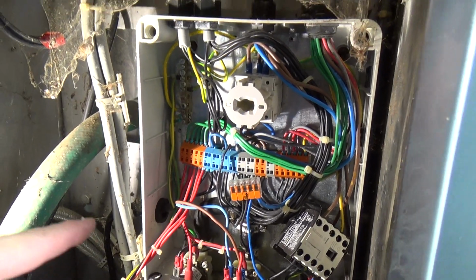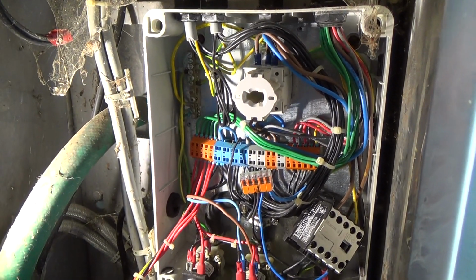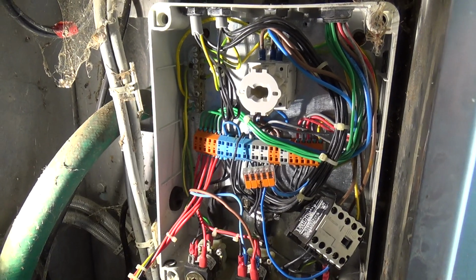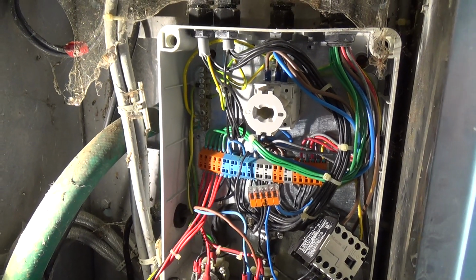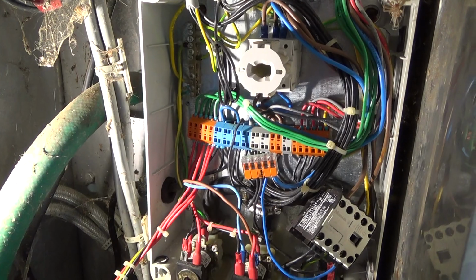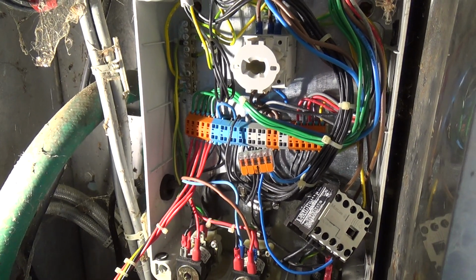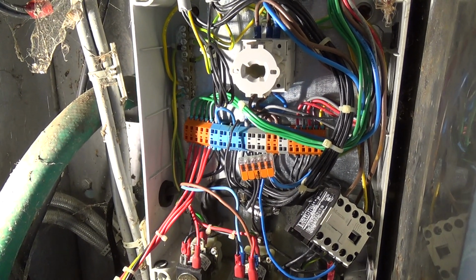Although probably that's going to be connected to the neutral in the control box up in the loft. So it's going to show a short, because even if it's not shorted, it's just going to go back to the incoming neutral again. So we'll probably have to get up in the box in the loft and turn the power off properly to that.